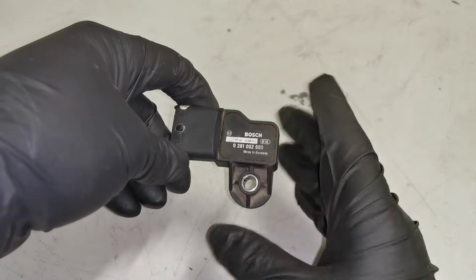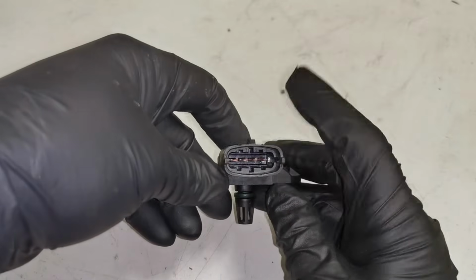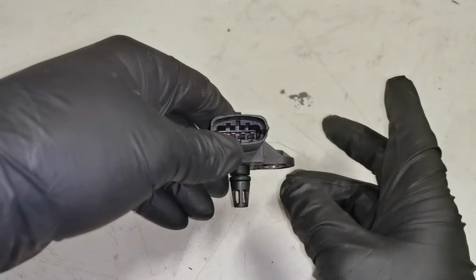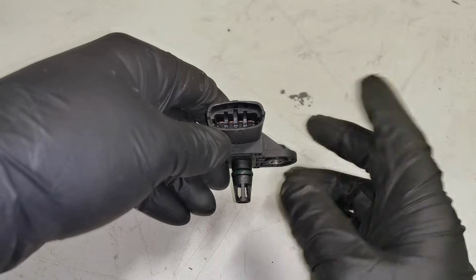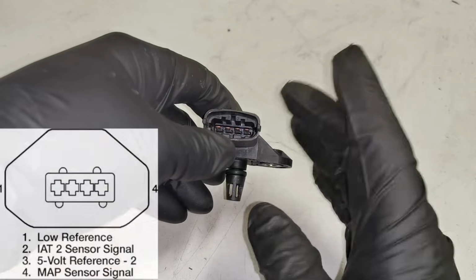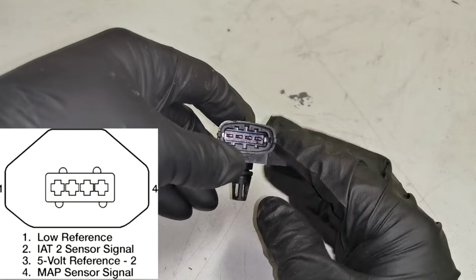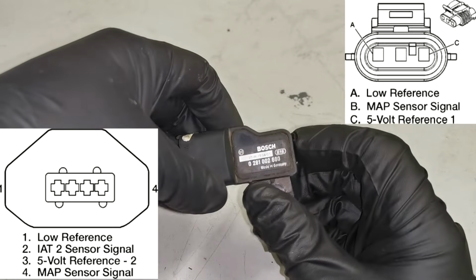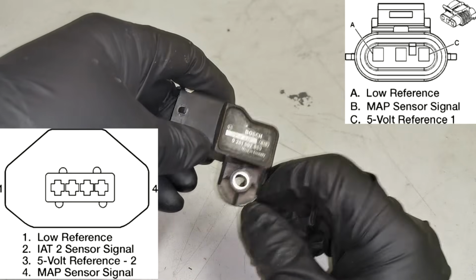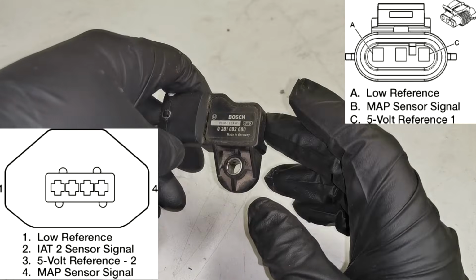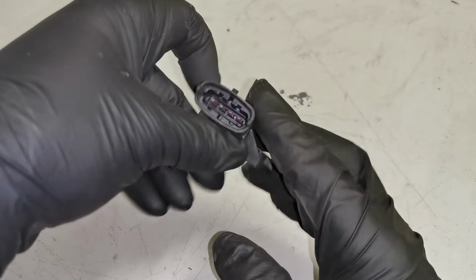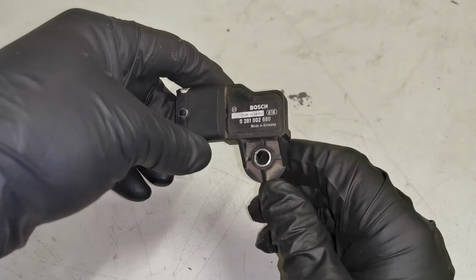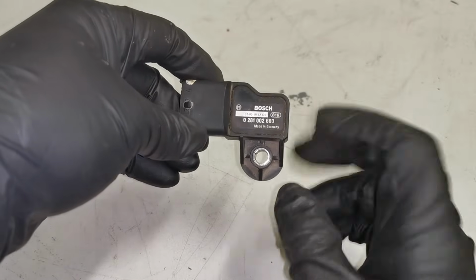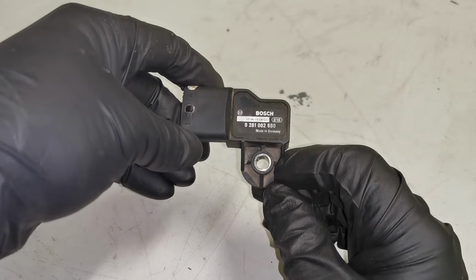Okay, so the difference between a 3-wire and a 4-wire. A 3-wire has the 5-volt reference wire, it has a low reference or a ground wire, and the signal wire is also there. The additional 4th wire is the intake air temperature, and that is the only difference between a 3 and a 4-wire. You are getting a temperature reading on the 4-wire map sensors as well.